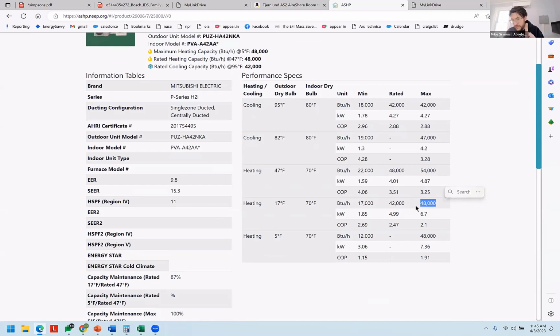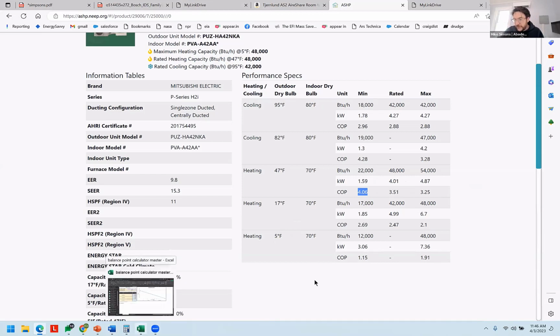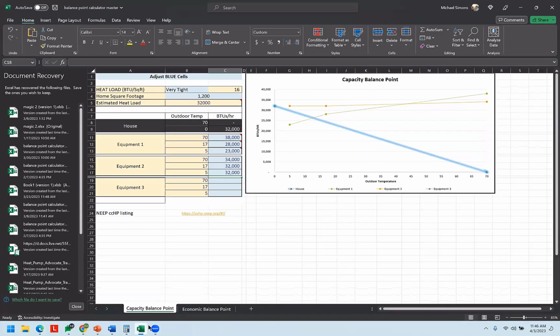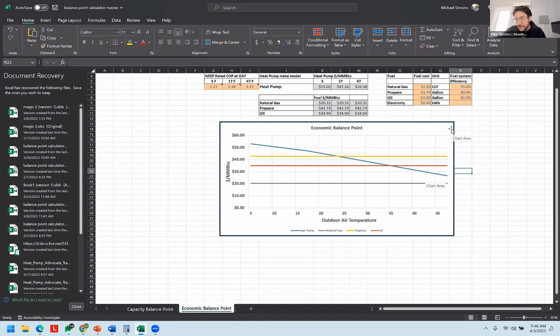So for your downstairs, there's nothing wrong with putting a Carrier heat pump or a Bosch heat pump on top of a natural gas-fired furnace if someone did want to have resiliency and redundancy, because polar vortexes are real and snowpocalypses are real. Also, it's worth highlighting that when it's 5 degrees outside, the performance of a heat pump is still very efficient, almost 200% efficient, but 200% efficient isn't 400% efficient. It's working really hard at those temperatures. So for cost reasons, they may want to run a natural gas-fired furnace during extreme cold weather. And that blows through the coil that's on top? Yep, you got it. That's 100% compatible, made to do it.